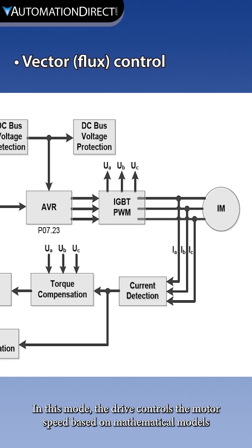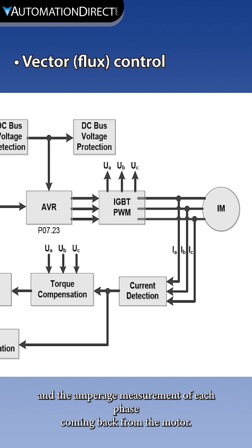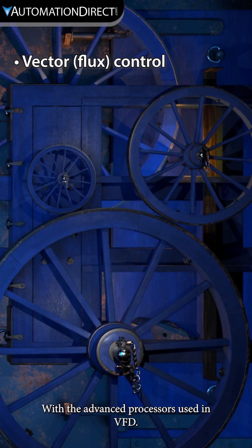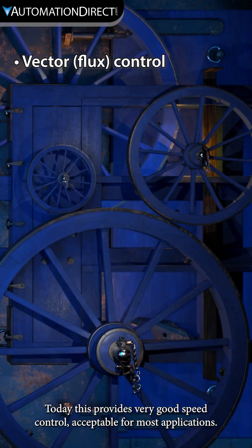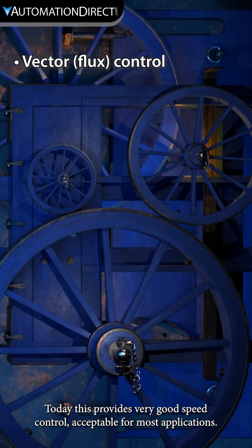In this mode, the drive controls the motor speed based on mathematical models involving the VFD voltage and frequency output and the amperage measurement of each phase coming back from the motor. With the advanced processors used in VFDs today, this provides very good speed control, acceptable for most applications.